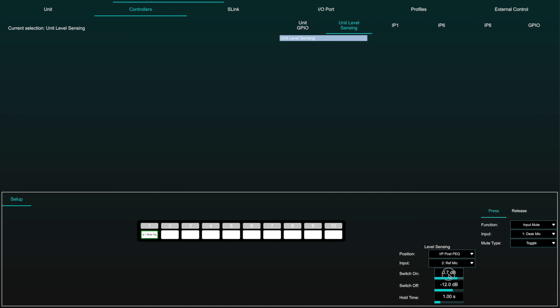Switch on sets the level at which the virtual switch will be activated and the function attributed to press will be triggered. Switch off determines the level at which the virtual switch will be deactivated and the function attributed to release will be triggered.